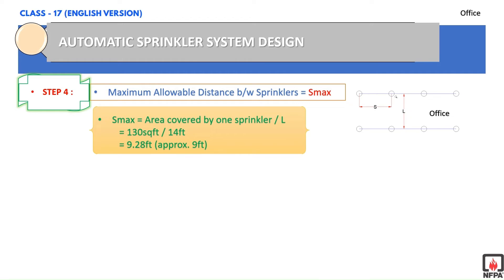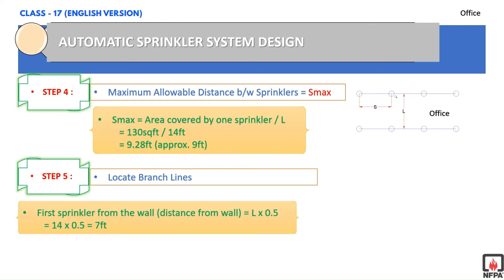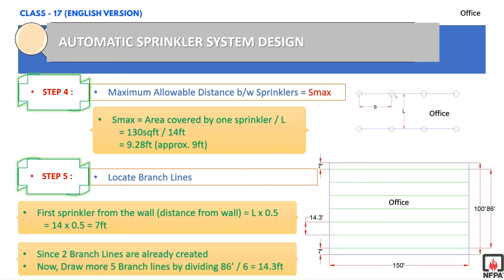Step 5: We need to draw the branch lines. From Step 2, the number of branch lines is 7 and the actual distance between branch lines L is 14 feet. The first sprinkler distance from the wall shall be half of L — that is L multiplied by 0.5 — which equals 7 feet. As you can see in the drawing, the 2 branch lines from the walls are at 7 feet distance. The remaining 5 branch lines are placed by dividing the remaining 86 feet by 6, giving a spacing of 14.3 feet, as shown on screen.